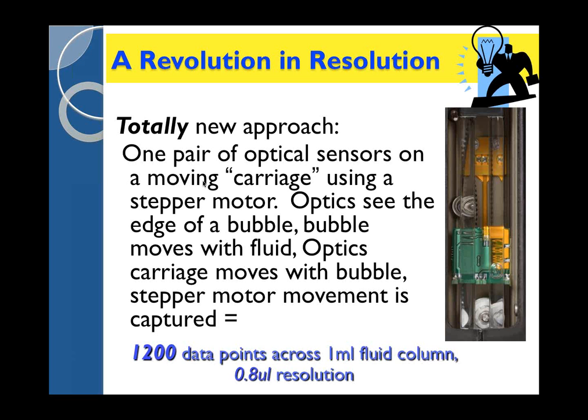So the carriage, with the optical sensors on it, moves using a stepper motor. The optical sensors see the edge of the bubble, and the bubble moves as the IV pump is pushing fluid through. The optics carriage moves with the bubble, and the stepper motor movement is captured. And in essence, what we have with that new approach is 1,200 data points across that same 1 milliliter fluid column, providing us with 0.8 microliter resolution in terms of what we can see in fluid travel.